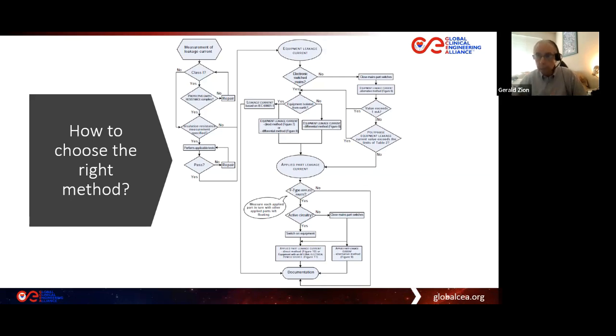This decision tree or flow chart appears in the IEC 62353 standard as the way that you will choose the testing method. And when will you choose that testing method? When you are doing your acceptance testing, incoming inspection, when the medical device is new to your facility, even if you have other brands and models of that medical device also in your inventory already, you still will need to come up with which testing method you will apply. And then that needs to be spelled out in the testing procedure and the policy about how you will do electrical safety testing and when.